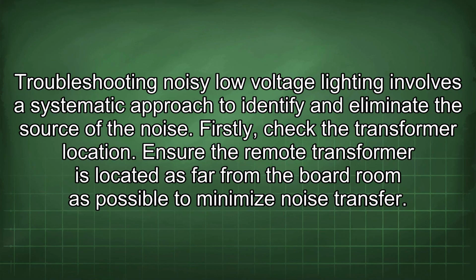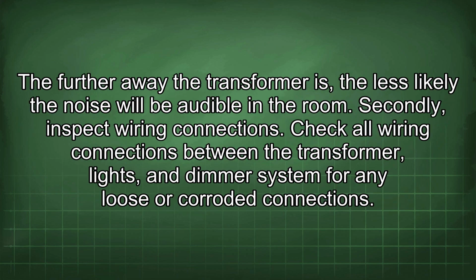Troubleshooting noisy low-voltage lighting involves a systematic approach to identify and eliminate the source of the noise. Firstly, check the transformer location. Ensure the remote transformer is located as far from the boardroom as possible to minimize noise transfer. The further away the transformer is, the less likely the noise will be audible in the room.